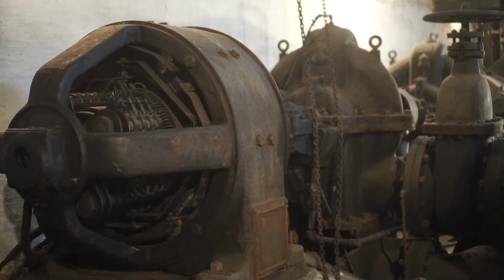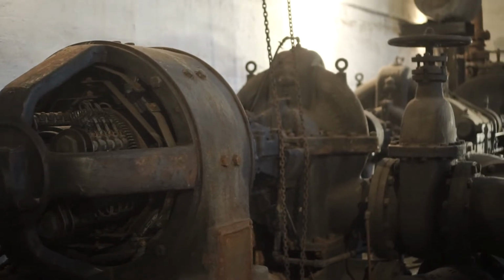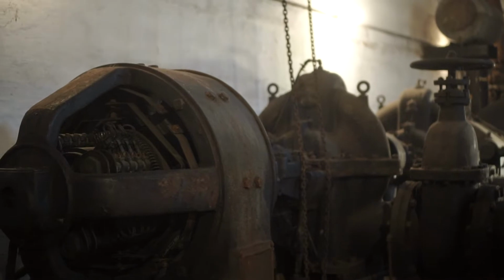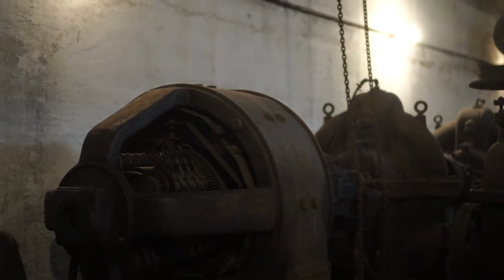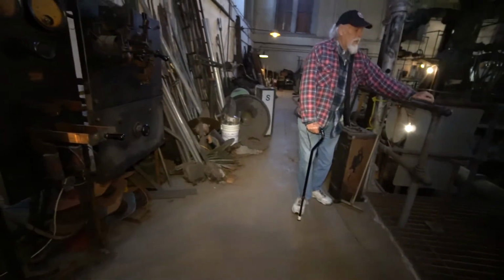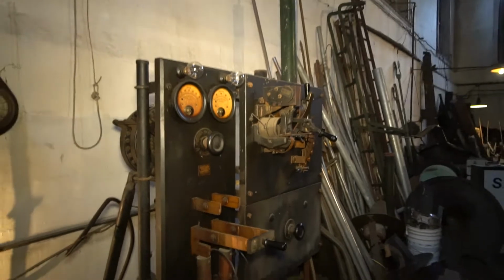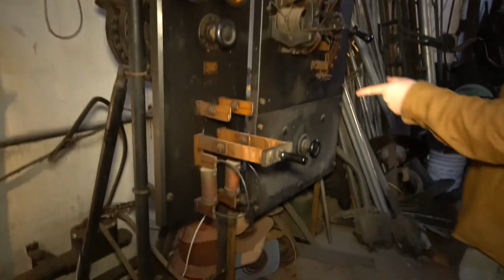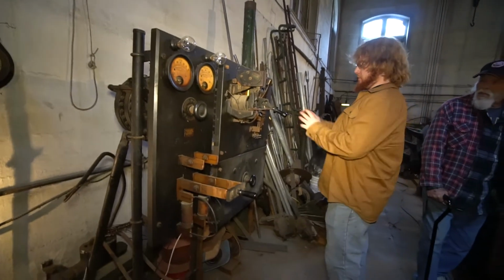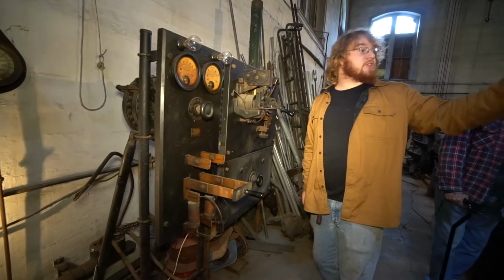Now, mind you, to get this thing spinning, you already have to now be spinning 2 centrifugal pumps completely dry, which is what that's supposed to do. But now that that's spinning, it's making electricity. Now the electricity comes all the way back this way, through this panel. There's a few things here. There's a main disconnect, which is what connects to that generator. Then you've got a motor starting panel. There's also a field rheostat for controlling the exact voltage on that dynamo.